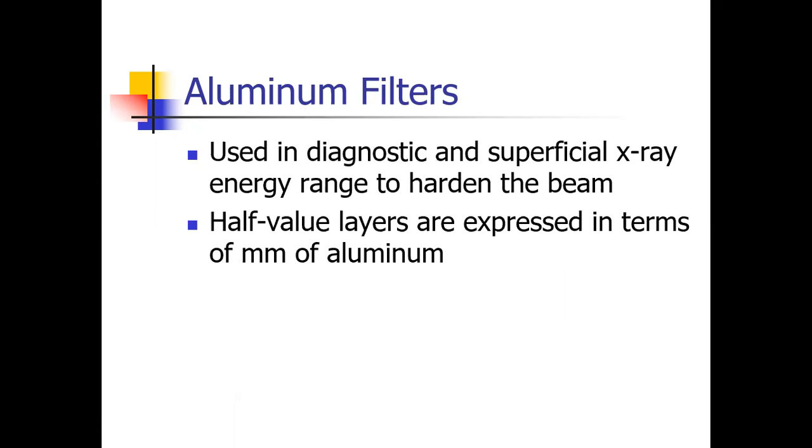Aluminum filters are used in the diagnostic and superficial X-ray energy range in order to harden the beam. And the HVL is expressed in terms of millimeters of aluminum, since that's what you're using.